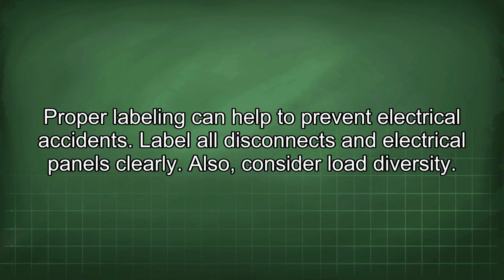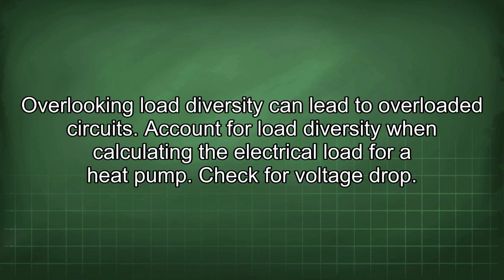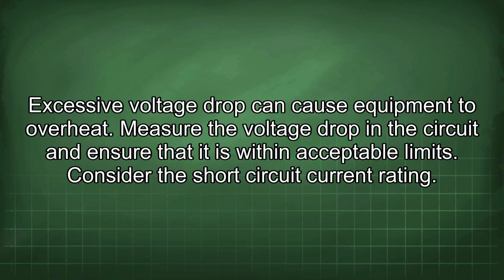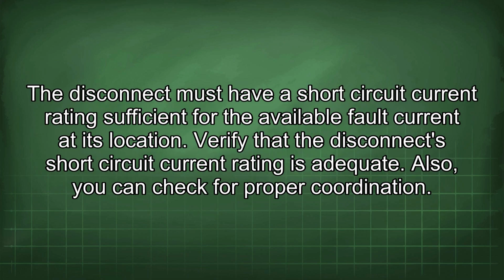Also, consider load diversity. Overlooking load diversity can lead to overloaded circuits. Account for load diversity when calculating the electrical load for a heat pump. Check for voltage drop. Excessive voltage drop can cause equipment to overheat. Measure the voltage drop in the circuit and ensure that it is within acceptable limits. Consider the short circuit current rating. The disconnect must have a short circuit current rating sufficient for the available fault current at its location. Verify that the disconnect short circuit current rating is adequate.